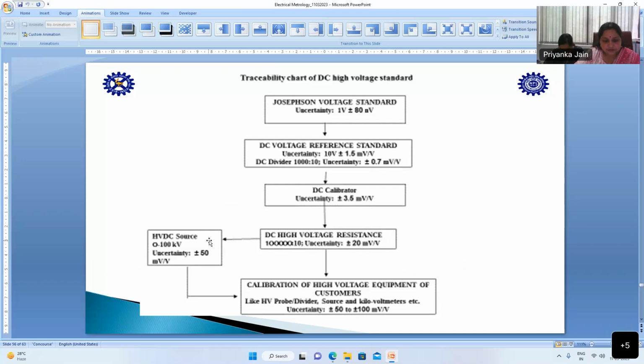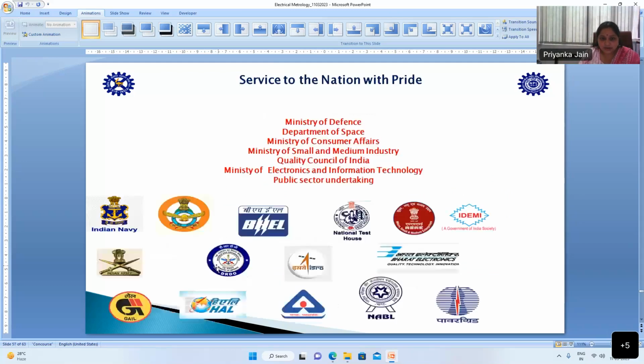Then we have a high voltage DC source, with uncertainty in the range of 50 millivolt per volt, and calibration of high voltage standards. We have high voltage probes, dividers, sources, and other kilovolt meters. We are providing services for these calibrations. So we are going to add more shortly.